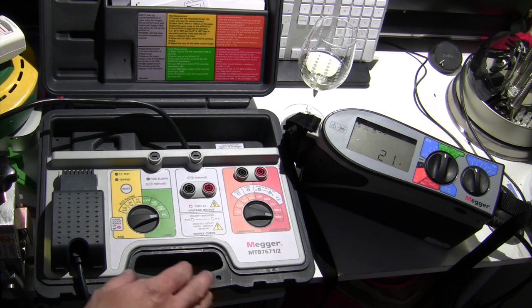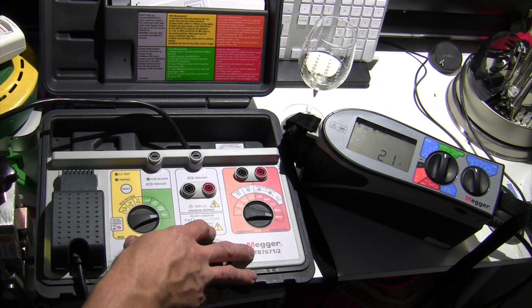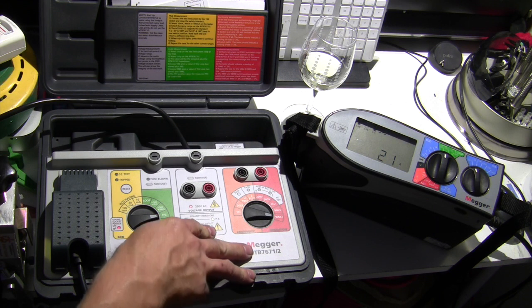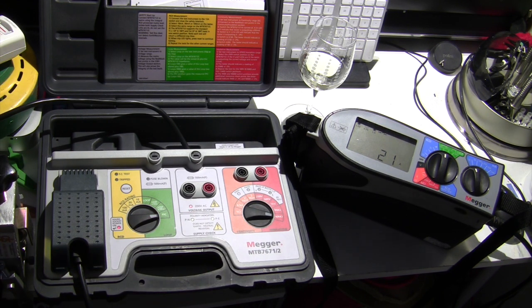But I just want to know on a sort of weekly or monthly basis, are the basics, the nuts and bolts tests I'm performing every day on continuity, RCD testing, earth fault loop impedance, insulation resistance, and all that sort of stuff, are they coming out as I expect? And that's what we use the check tester for.